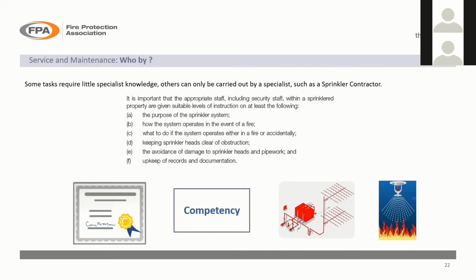I mean, they shouldn't think that all the sprinklers go off when you get a fire. Don't forget, it's only the ones that are activated by the heat. They should know what to do if the system operates in a fire or accidentally. If you're working in, say, a warehouse and your forklift truck driver knocks a sprinkler out in the rack, what do you do? Do you need to panic, or is it something you can control easily? You need to be able to keep your sprinkler heads clear of any obstructions, obviously, because if you put storage of goods too close to the sprinklers, they won't operate correctly, and you need people looking out for that.